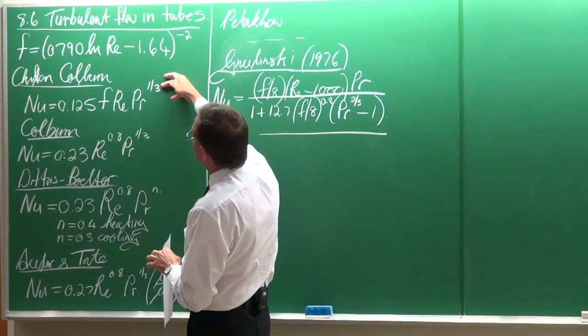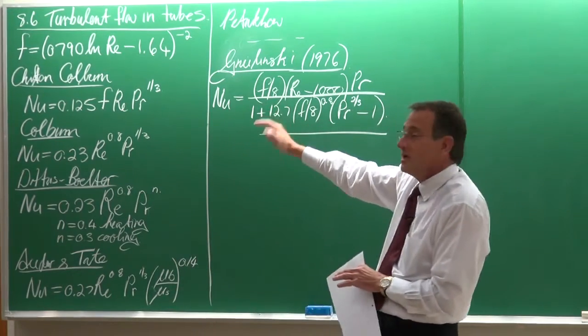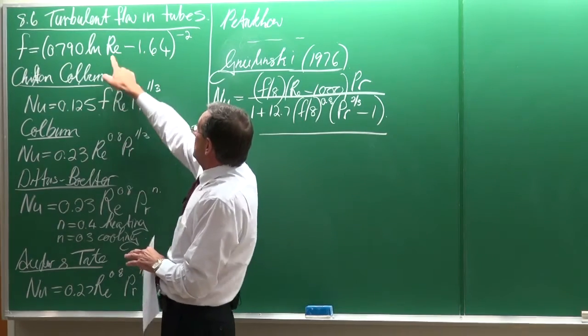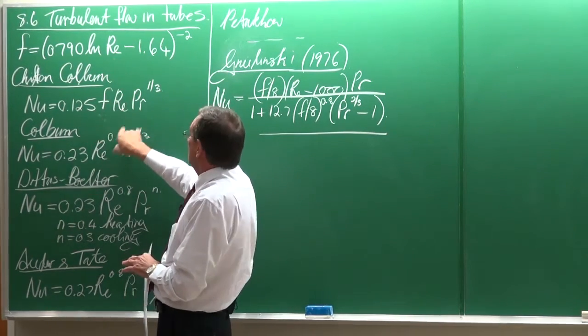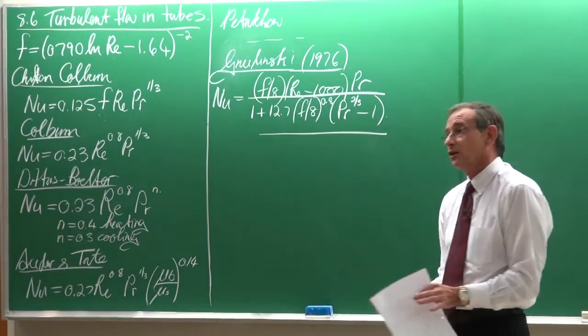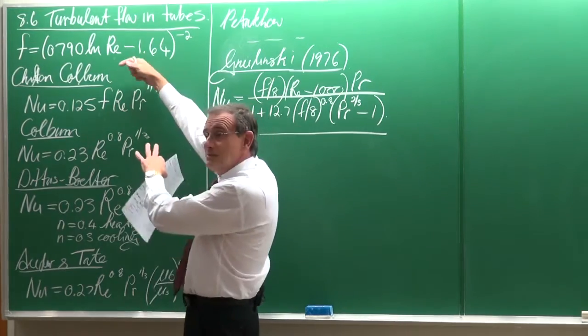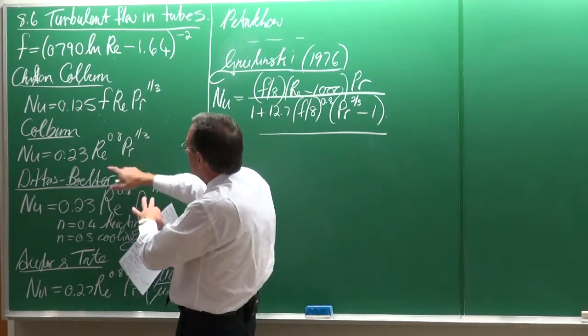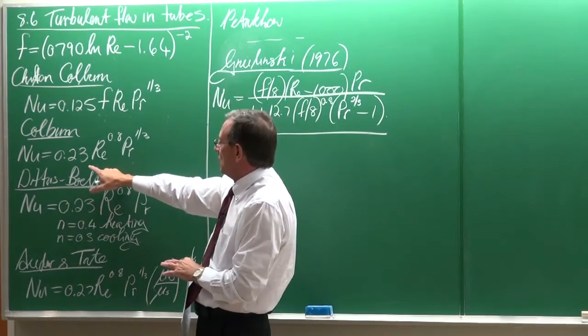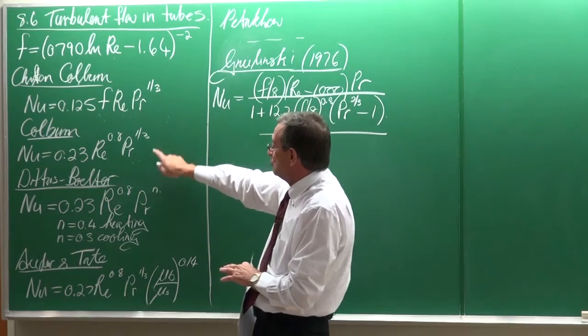you'll see that this friction factor equation is only valid for a certain Reynolds number range. So, now the first equation, almost 80 years ago, was developed by Chilton and Colburn, and this is the Chilton-Colburn equation. So, you can see, getting the Nusselt number, you must first get the friction factor, and you need the Reynolds and the Prandtl number, and then you can get the heat transfer coefficient from the Nusselt number. And then, with the same data set, people like Colburn developed an easier equation, this one, 0.23 Reynolds to the 0.8, and Prandtl to the third.